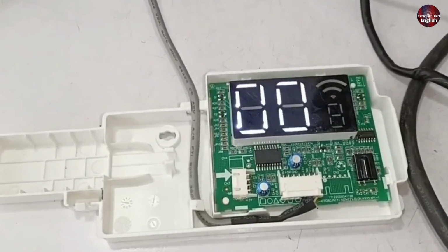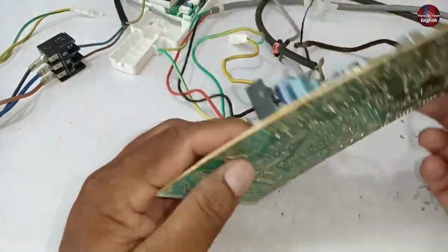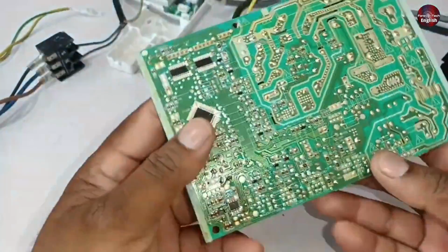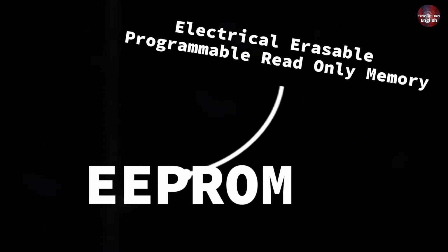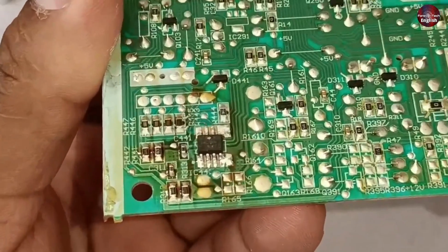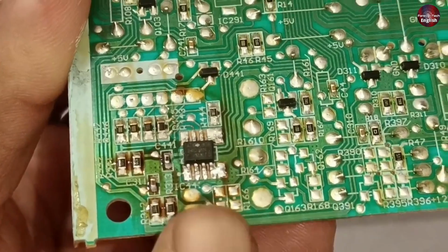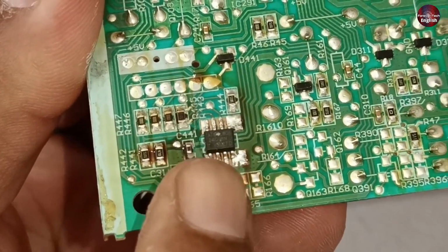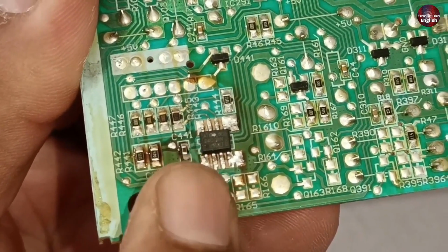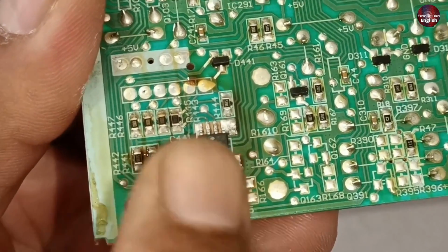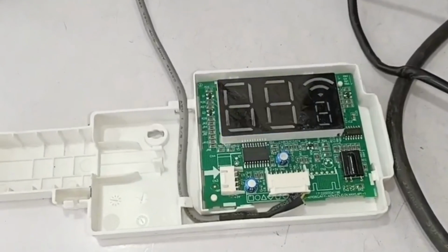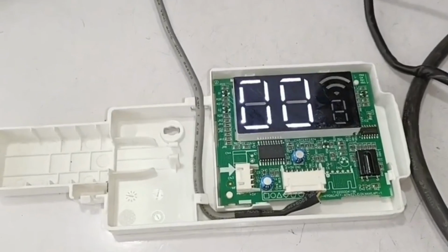EH00 is the indoor unit error. Most indoor units have flash memory systems. Technically, we call it EEPROM, and it stands for Electrically Erasable Programmable Read-Only Memory. This is the flash memory installed here in the PCB. Suppose it is corrupted internally, physically damaged, short-circuited, or does not have the operating voltages to operate it. In that case, an EH00 error can be displayed on the indoor unit.